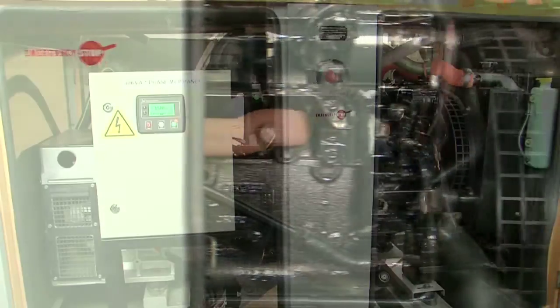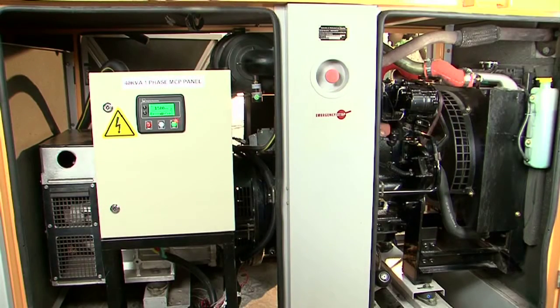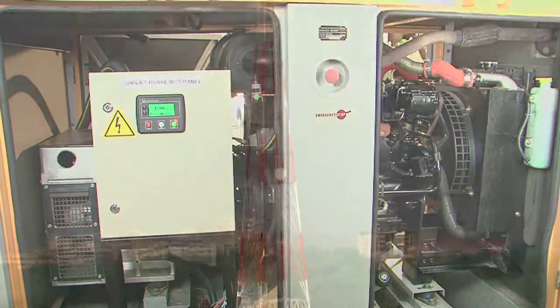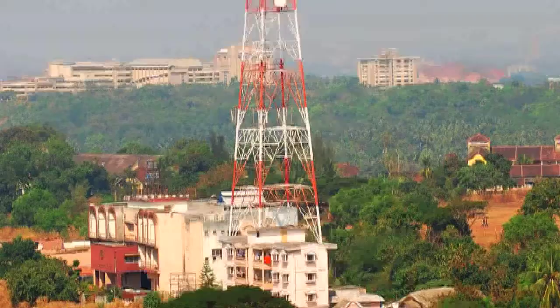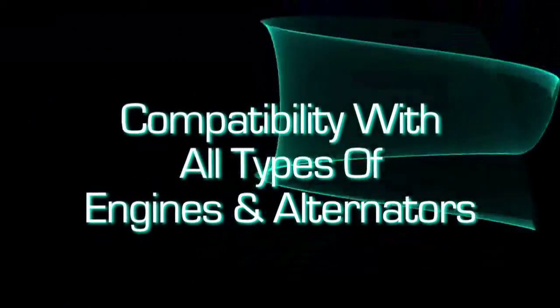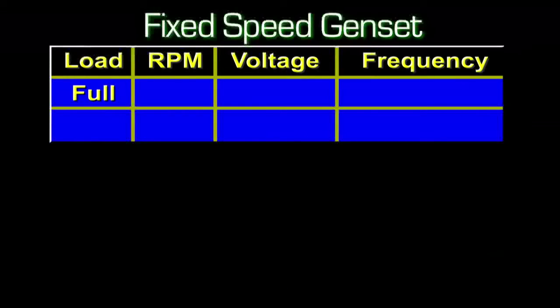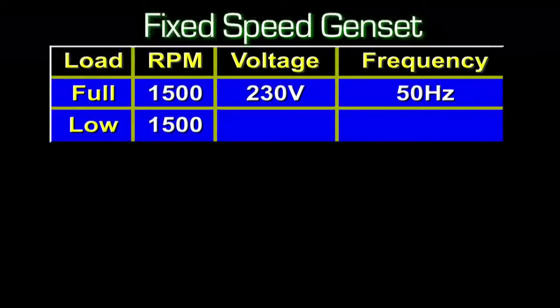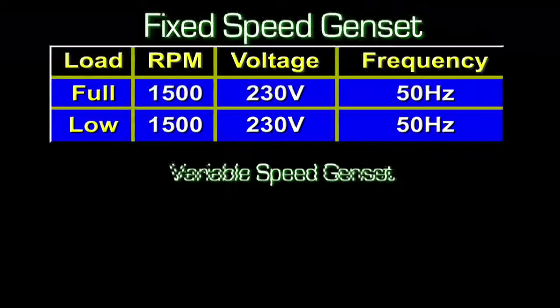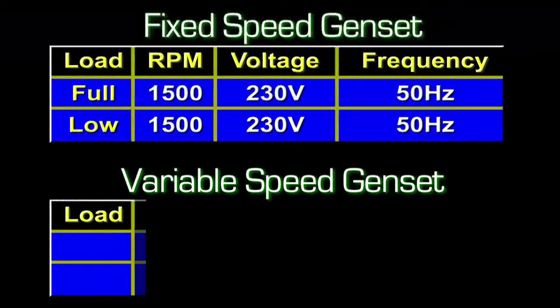As a result, within half a day, a fixed-speed telecom genset can be transformed into a variable-speed, fuel-efficient, fuel-saving telecom genset at the site itself. Compatibility with all types of engines and alternators. In a fixed-speed genset, the output voltage is 230 volt at 50 Hz. That's not the case with a variable-speed genset.